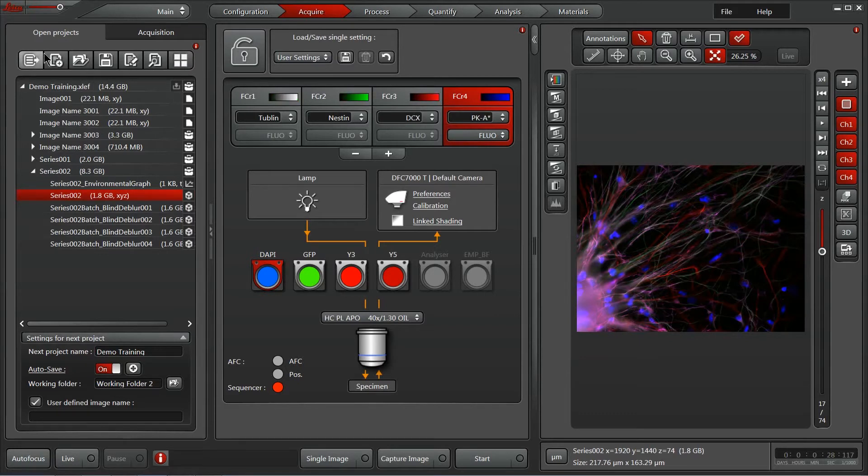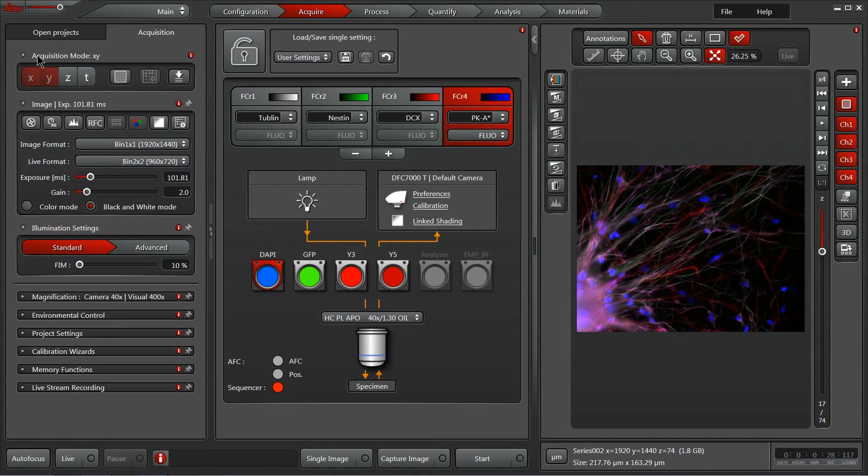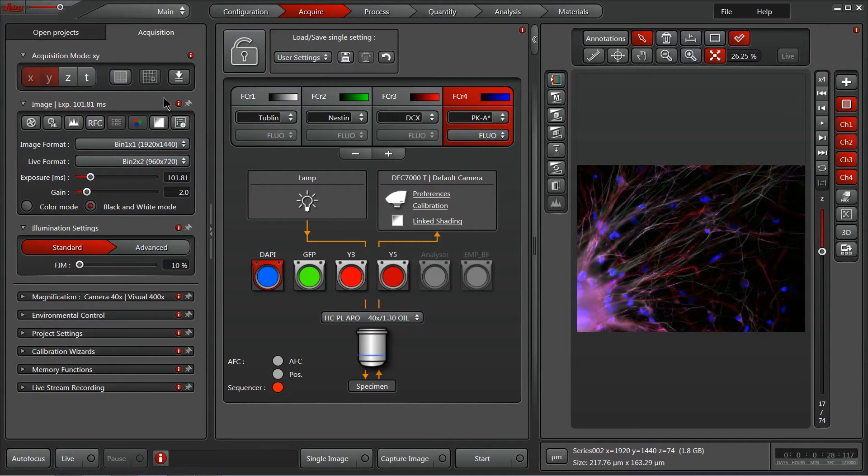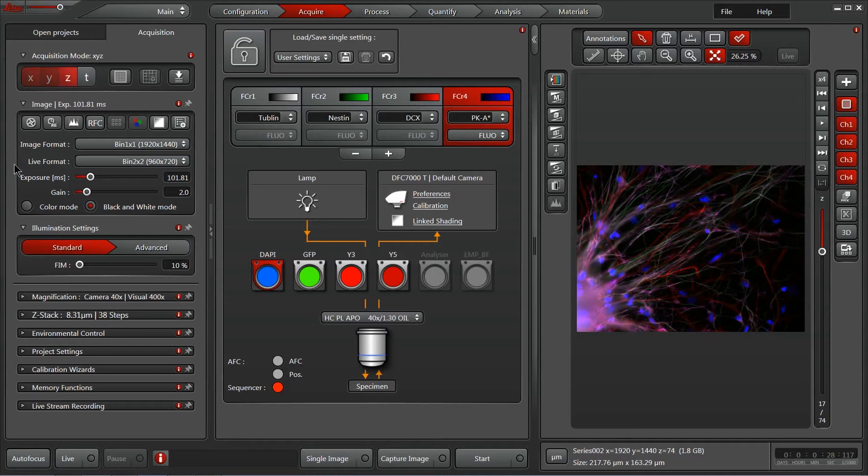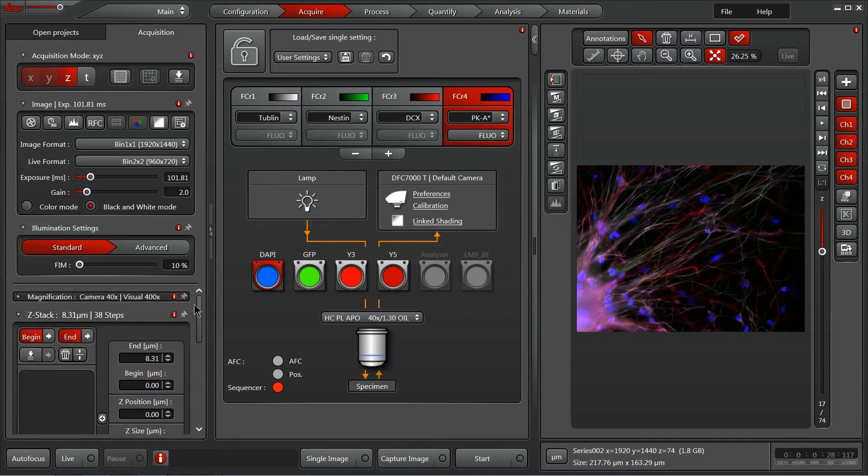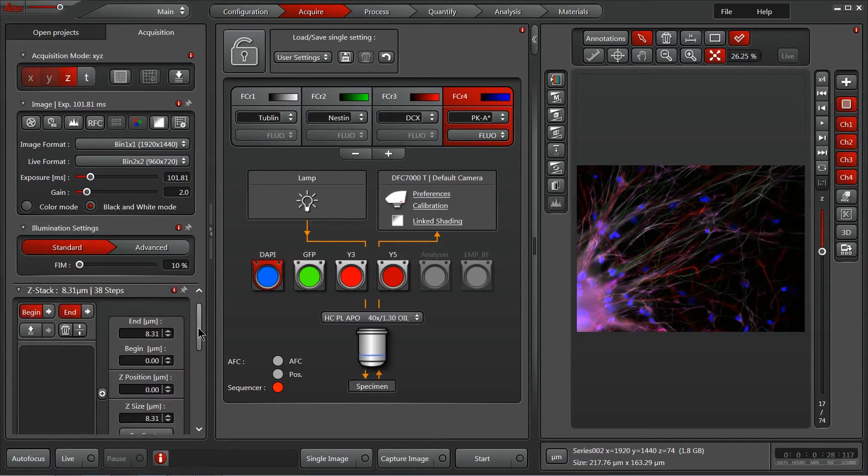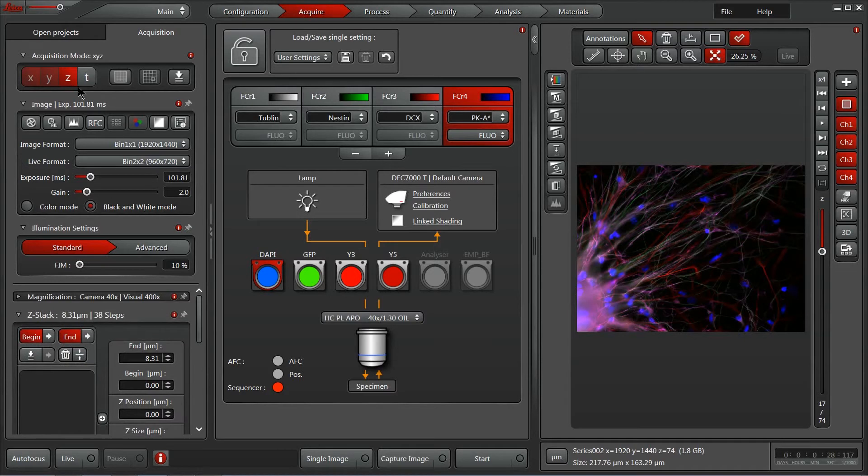Now let's continue into our acquisition tab. The first thing we'll see is the acquisition mode, where we control which dimensions will be included in our experiment. Here all the ones that are selected will be highlighted in red. When you add an additional dimension, the new dialog appears in the list below, and you can address that dialog to assure that it's capturing the range within the dimension that you like.